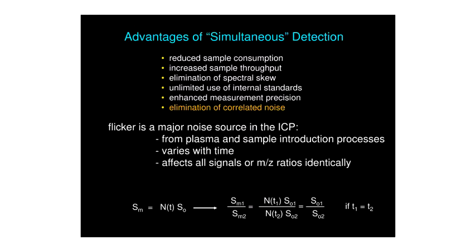If you're looking at two different isotopes of the same element and trying to match them, with a sequential system some period of time passes before the second isotope can be recorded, and the intensity has changed either up or down depending on where you are on the peak. That introduces spectral skew, which skews the isotope ratios. With a truly simultaneous measurement technique, that problem vanishes.